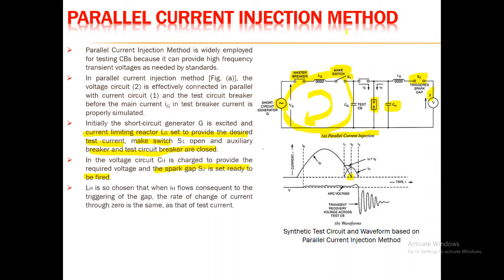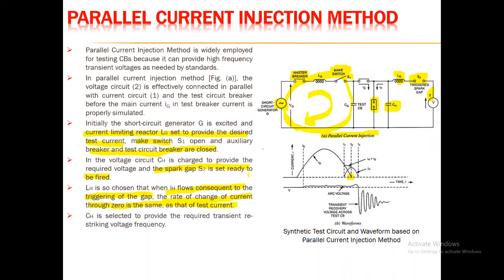LH is chosen so that when the high voltage current IH flows consequent to the triggering of the gap, the rate of change of current through zero is the same as that of the test current IG. CH is selected as the high voltage capacitor to provide the required transient restriking voltage at the natural frequency.